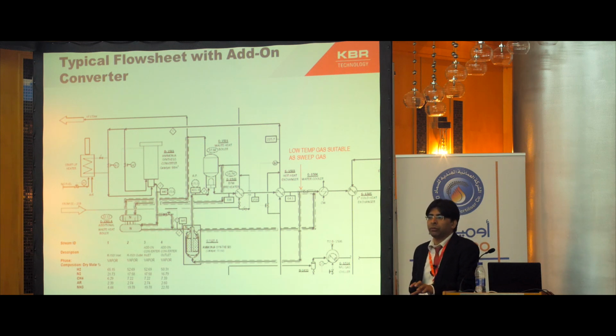The amount of boiler feed water flowing through the water jacket is very small. It's only 4 tons per hour of water. Some of the water is used to generate steam in the top shell, and the rest of the water is drained back. So for small savings, there is very little potential in taking the heat from this boiler, from this water jacket.